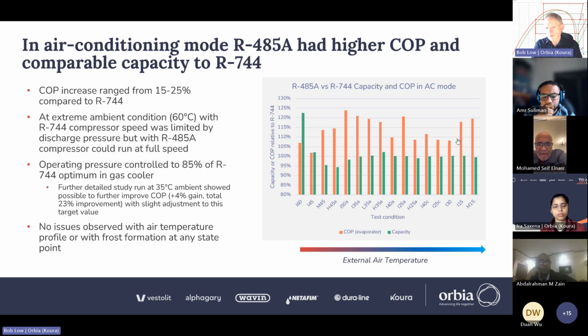And in terms of evaporator temperature distribution, we saw no issue with air temperature quality, and no issue with frost formation. So very encouraging results, and it would be directly transferable to, for example, a stationary cycle running in sort of 0C evaporator with ambient air as the heat sink onto the gas cooler.